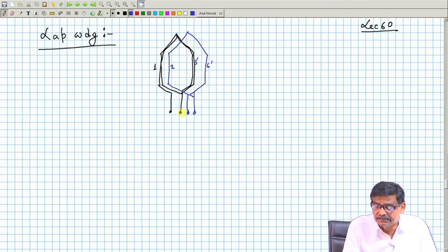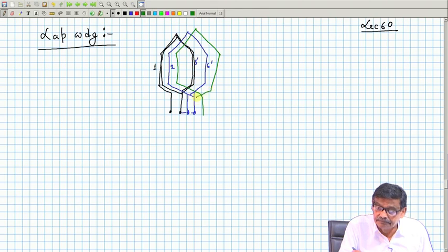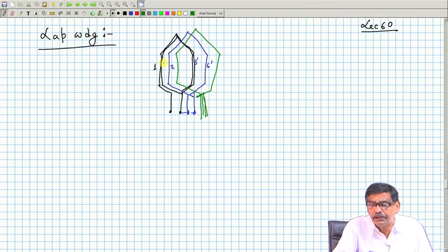So, you see, and these coils I am connecting in series. Second coil is on the lap of the first coil. Similarly, third coil will be here in slot number 3. I think you have got the idea, is it not? Start and finish of the third coil will be on the lap of the second coil. That is why it is called a lap winding. In this way, I have proceeded to complete the winding of the coils.